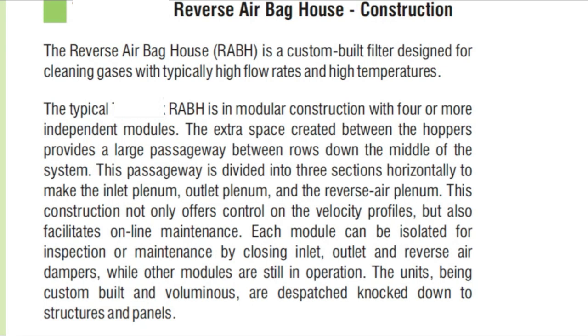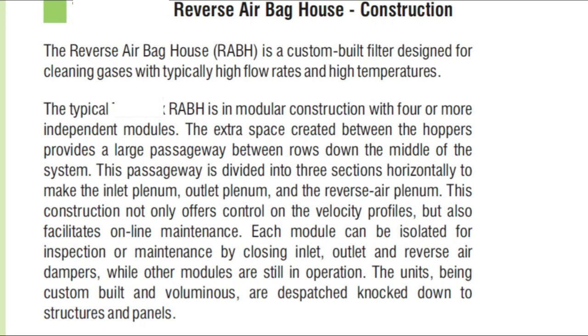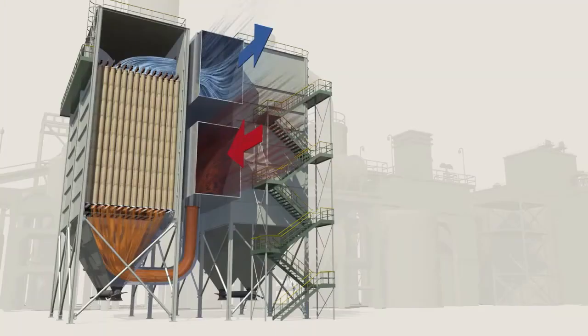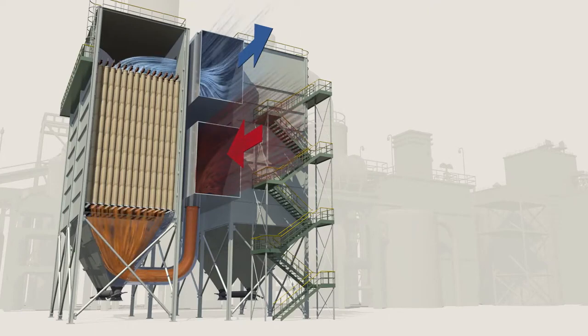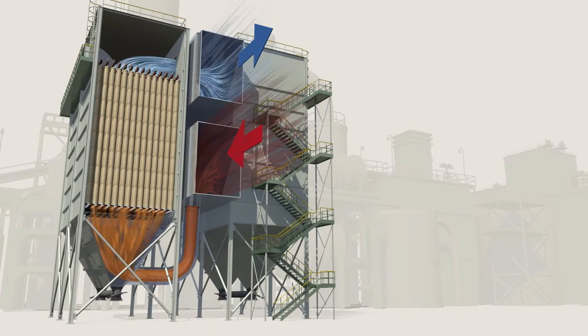This passageway is divided into three sections horizontally to make the inlet plenum, outlet plenum, and reverse air plenum. This construction not only offers control on the velocity profiles but also facilitates online maintenance. Each module can be isolated for inspection or maintenance by closing the inlet, outlet, and reverse air dampers while other modules are still in operation. That is the advantage of RABH over a standard bag filter.